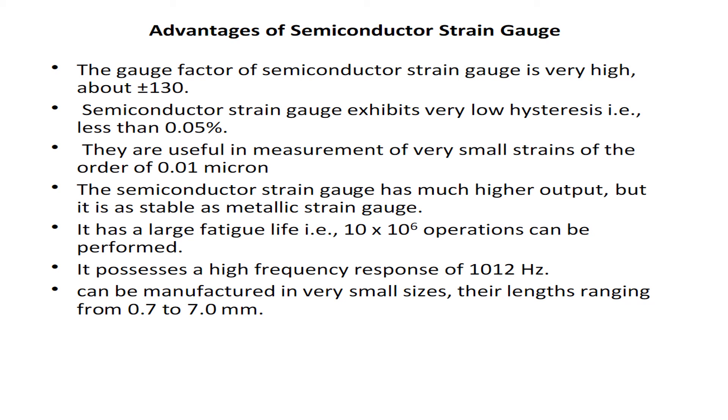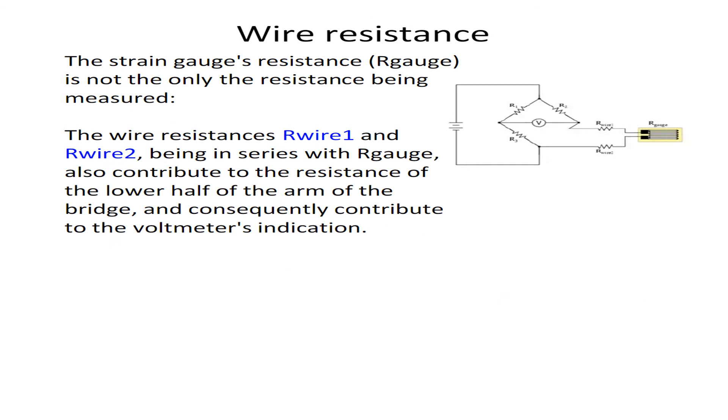The semiconductor strain gauge has much higher output but is as stable as metallic strain gauge. It has a large fatigue life: 10 × 10⁶ operations can be performed. It possesses a high frequency response of 10¹² hertz. They can be manufactured in very small sizes, their length ranging from 0.7 to 7.0 millimeter.